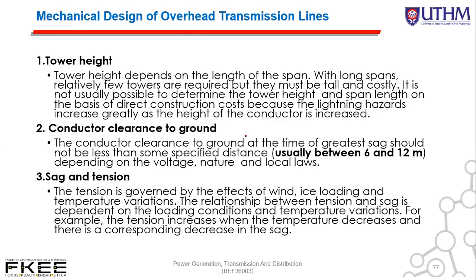Number two, conductor clearance to ground, needs to be considered. The conductor clearance to ground at the time of greatest sag should not be less than some specified distance, usually between 6 and 12 meters. So if you look back at the exercise before, is it allowable or not? Depending on the voltage, nature, and local laws.